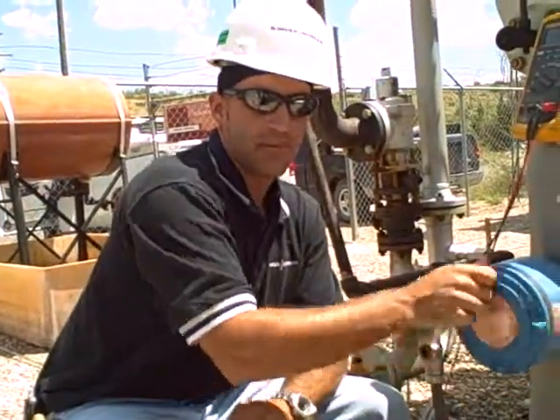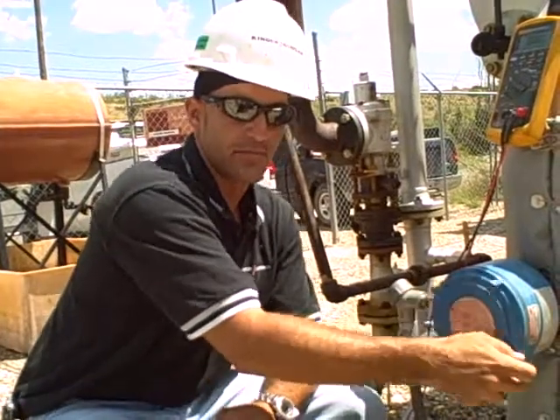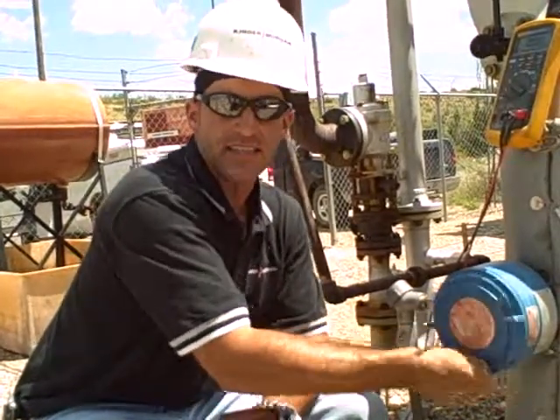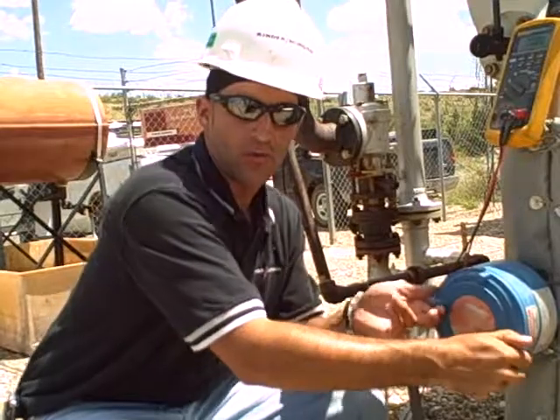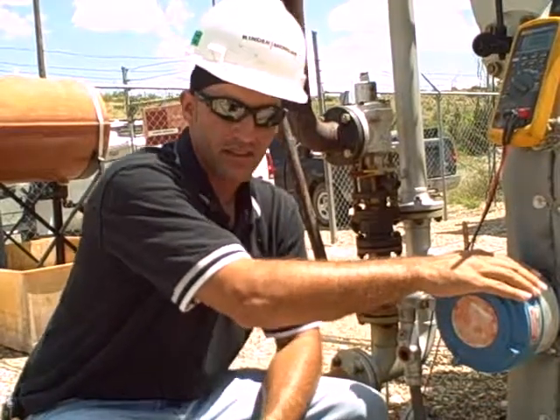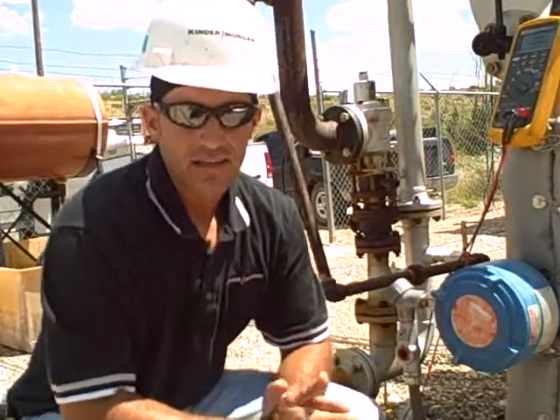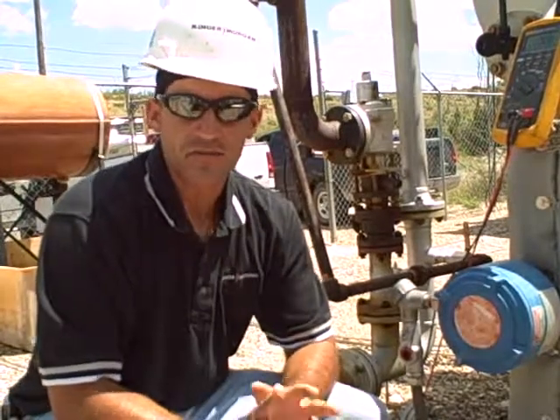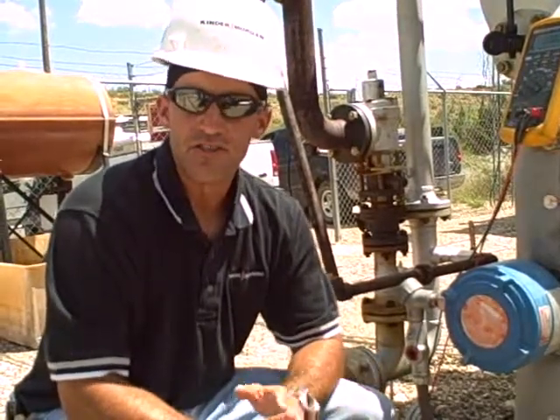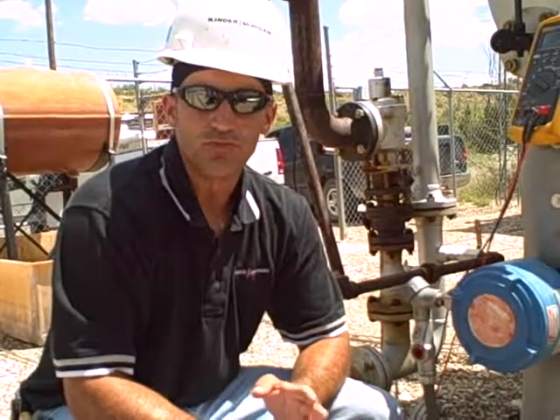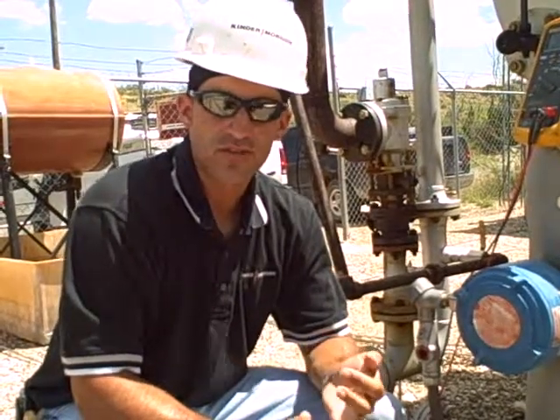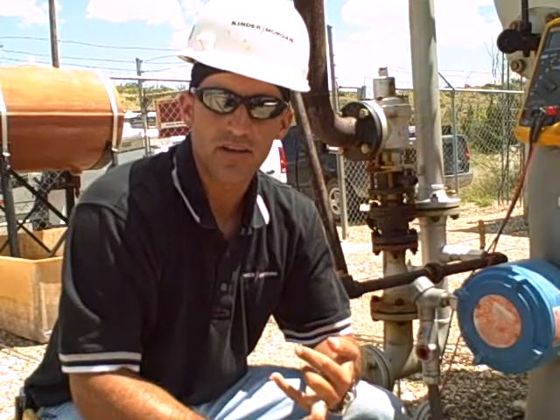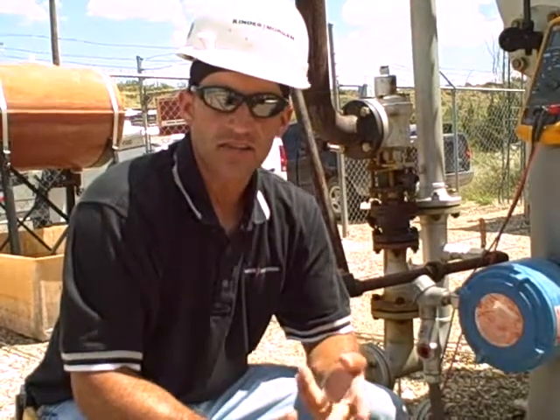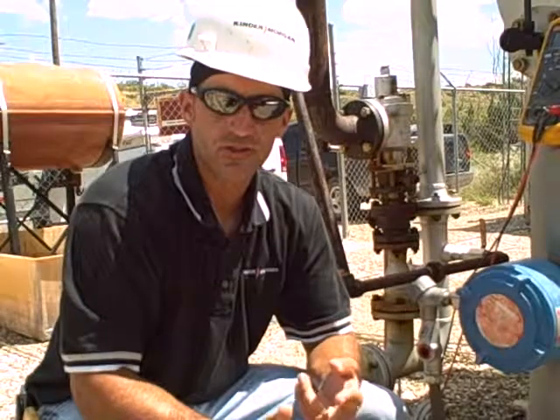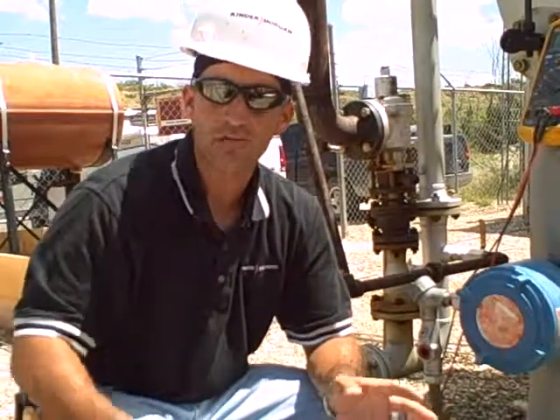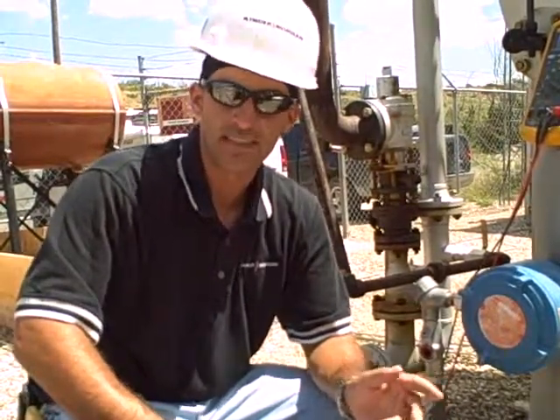One thing I want you to remember about today is that the BS&W Probe uses capacitance to measure the amount of oil and water that's going through this line right here. The percentage of oil and water is used by the operators to set their levels in their vessels, know how much they need to adjust their chemical, and so we can accurately count the amount of oil and water that each well makes out in Yates Field.